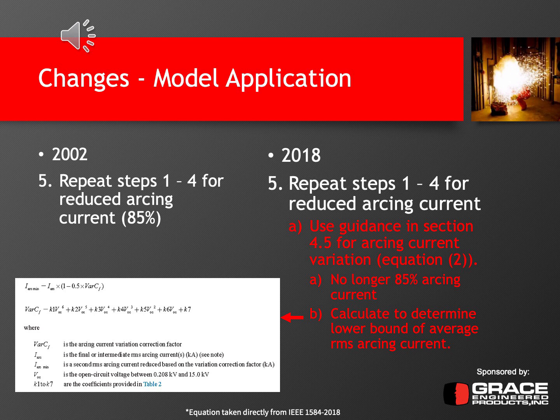So that all plays into calculating the IARC min. And then that IARC min is used as an input into the same equations from steps 2, 3, and 4. You wouldn't do step 1 because you've already calculated the arcing current. And now you're going to repeat steps 2, 3, and 4 with the minimum arcing current based on this equation.